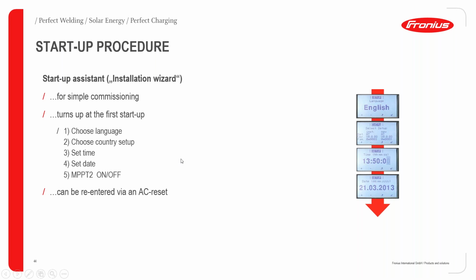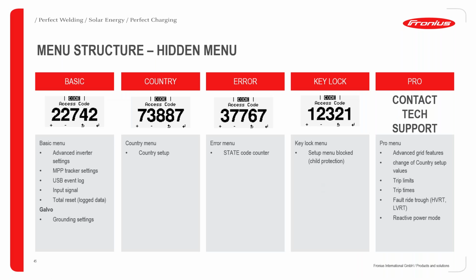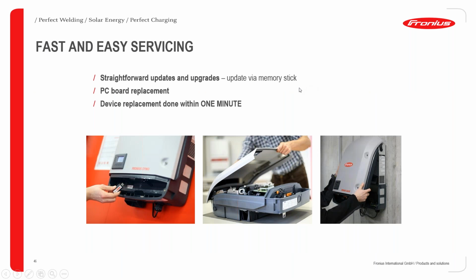And then I would now have to go through the startup assistance or startup procedure. So it's not much to it. Once you start up your inverter, go through the simple commissioning process, choose your language, choose your setup, make your time and date settings, and then you're done. So we have hidden menus, as you can see, the keys or the codes for basic menu, country setup menu, error menu, key lock menu, and for the Pro menu, because of the sensitivity of the settings here, you would have to contact tech support to be able to access these codes. Yeah, so in terms of servicing, servicing basically implies maybe an update, which is usually done via a memory stick or USB stick. PC board replacement is of course possible, and these replacements are easily done within 1 minute.